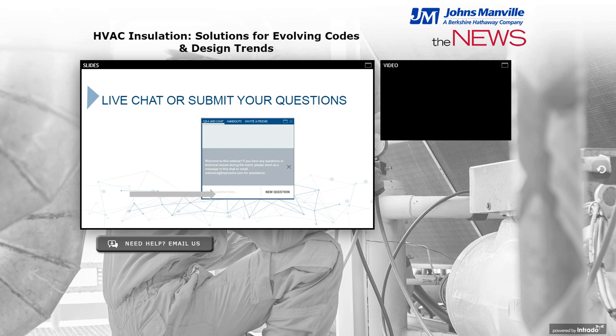There's some other ways guys do it. We've seen them wrap wire around it, and that helps hold it. As far as mastics go, I know there's white mastic out there. I don't know if there's black mastic, to be honest. There's tons of companies that produce mastics that are probably available. But when I see duct wrap installation failures relative to the tape, most of the time, in our experience, the contractor did not staple those seams and hold it together, and that fiberglass recovered and forced the tape seams to pull apart.